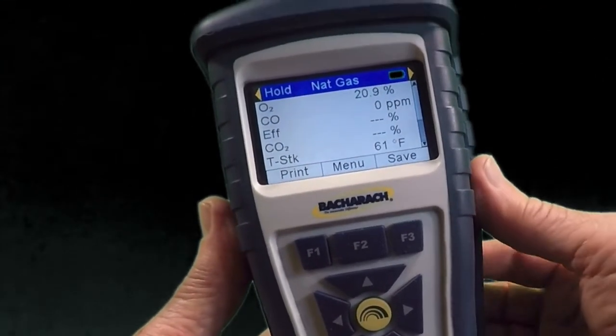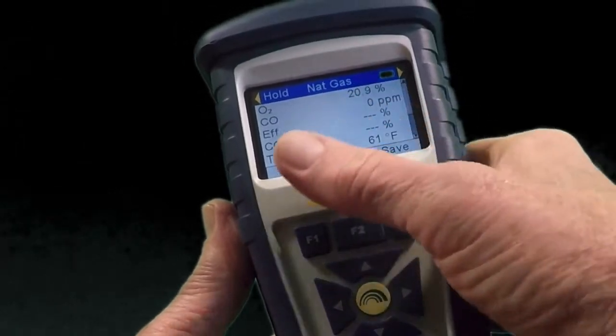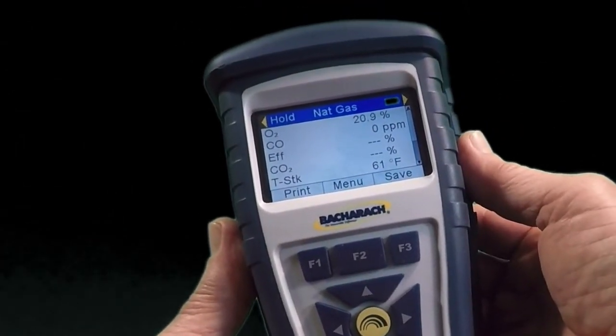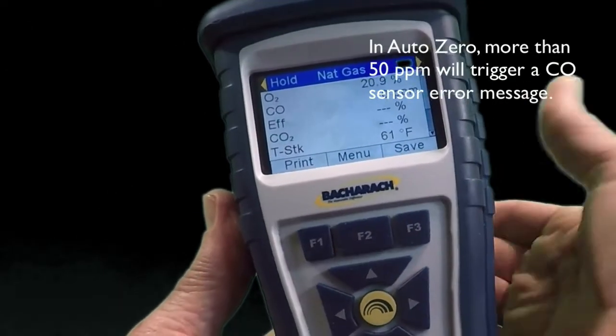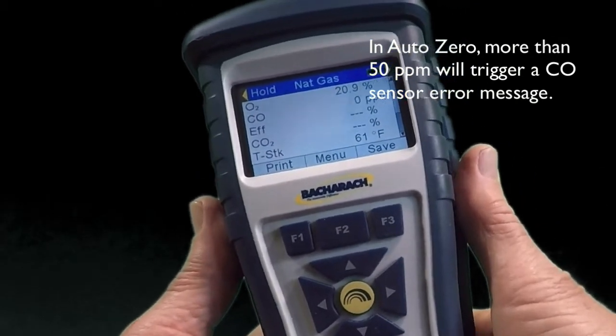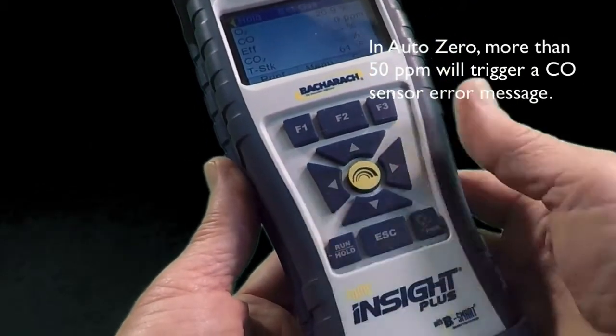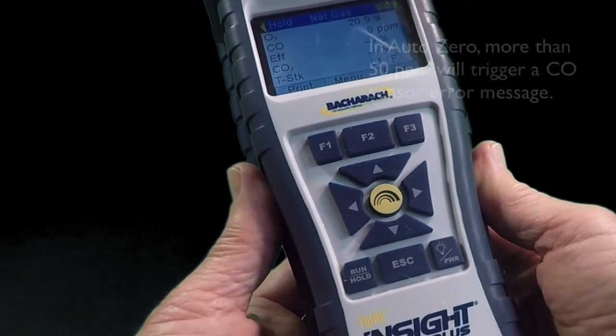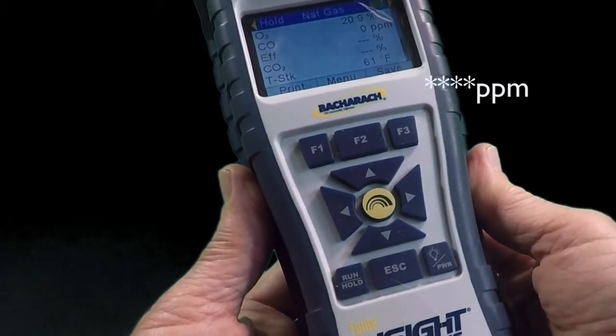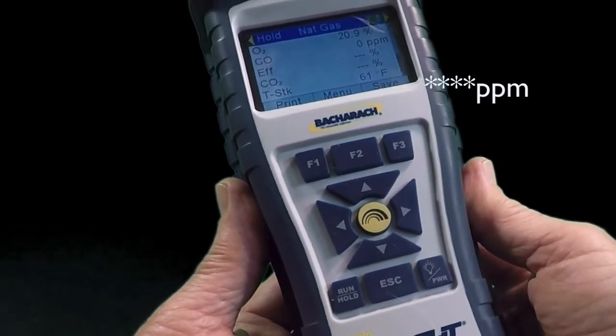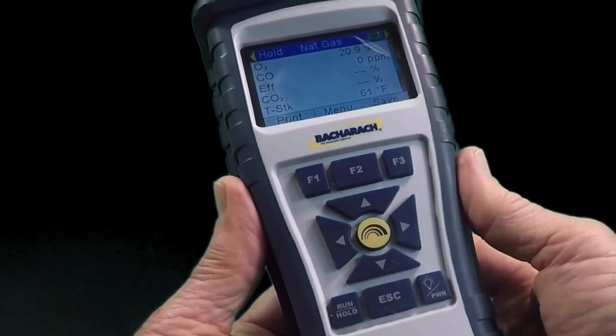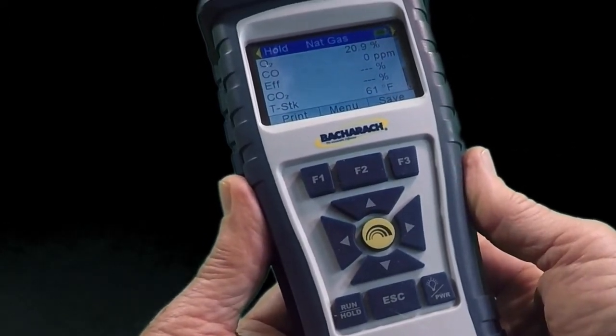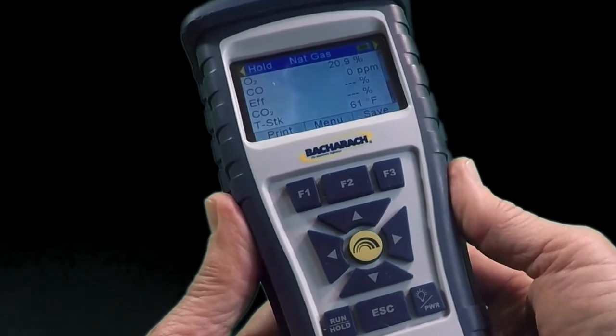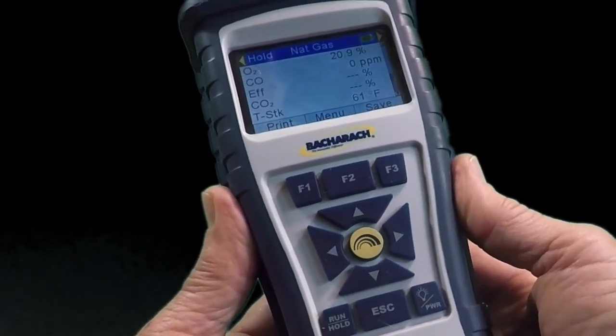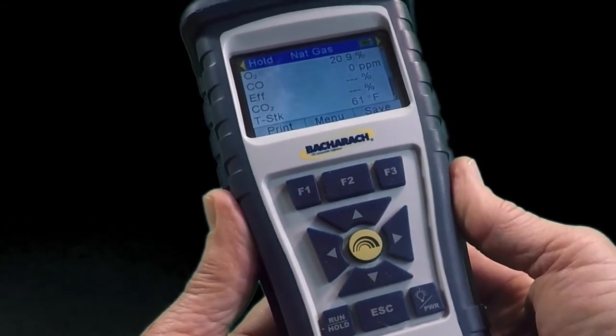Remember, if there's more than 50 ppm in the space, the instrument will come up with a CO sensor error message in the display when it finishes that 60-second countdown. And if you press the run button, it will display several asterisks before the ppm reading instead of a number. If this ever happens, you need to immediately evacuate to clean air, turn the instrument off, then on again. If it powers up without the error message, go back in the space and see what's going on.